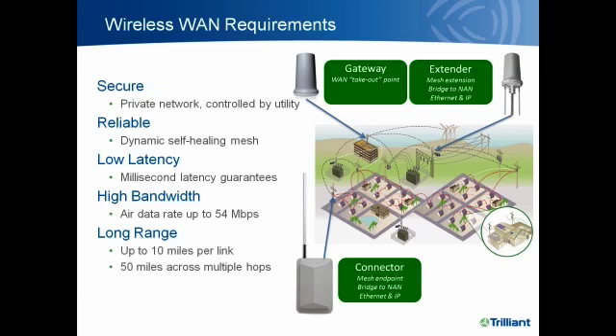This webinar is focused specifically on the Wireless WAN, so we're going to focus on its requirements. The very first thing we need to address is security. We're talking about a completely private network that is owned and controlled by the utility from end to end, with all of the encryption and authentication to ensure confidentiality, message integrity, and privacy. The network also needs to be reliable, featuring a self-healing mesh network that provides redundancy and fault tolerance. It also needs to provide low latency for grid reliability applications, the bandwidth to support applications like video monitoring, and long-range communications for links between substations that may be miles apart.